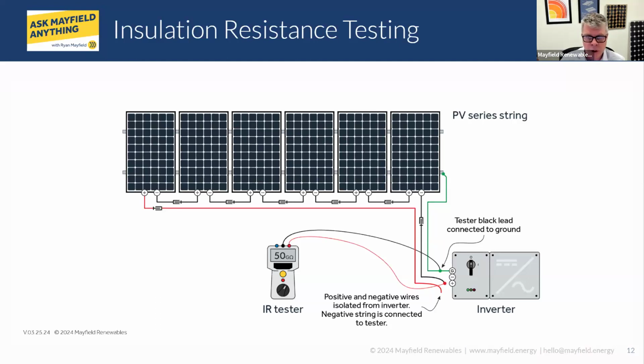Somebody had put in a comment about standards and which ones to be following. IEC has a standard that is specific to PV testing and commissioning. It's the number 62446, if that's something you're looking for. As I see it, part of the issue is we have a standard that says you should do insulation resistance testing, or you should measure your conductors and you can measure your array, but it doesn't tell you how to do it. It just presumes that everybody knows how to do it. If you own the tool, then you must know how to do it.